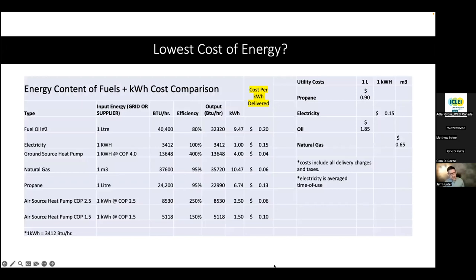So I don't want to confuse this, and putting up a chart with numbers is a little bit risky as far as losing our point in perspective. But when we talked about what is energy, and equating that all to kilowatt hours, getting us onto the same playing field, right? I can talk about a furnace that's on natural gas, a furnace that's on propane or fuel oil, and relate that all back to energy as kilowatt hours. And that's what we've done in this chart. We know how much energy is in a liter of oil. We know how much energy is in a liter of propane. We know how much energy is in a cubic meter of natural gas. And that's what we've listed out here.